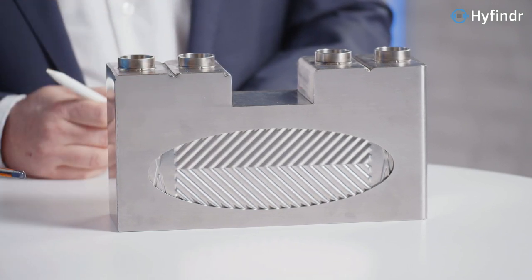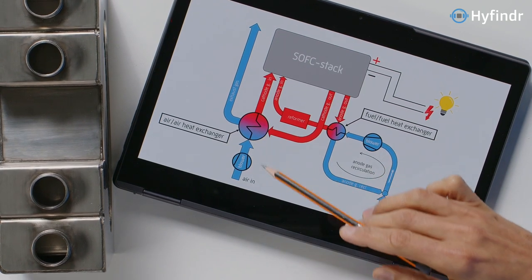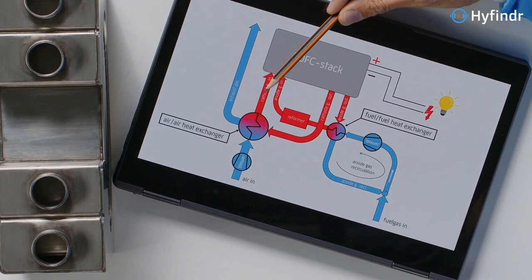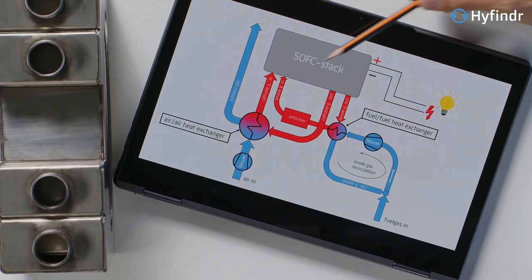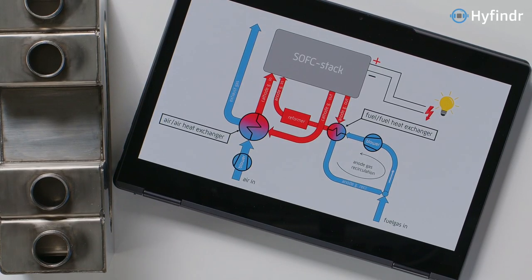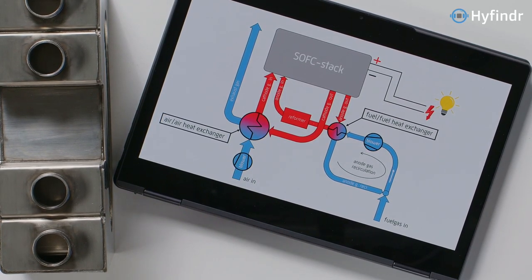What about the temperature — what's the typical delta T across this? When it comes to the air, we enter at ambient temperature. And so air coming in here at ambient temperature — it's heated up to about 700 degrees. That can be 700 degrees. On the other side you need some delta in temperature when you want to increase to this level. The incoming gas needs to be hotter, and it's cooled down to about 150 to 200 degrees Celsius. It comes in with about 800 degrees.